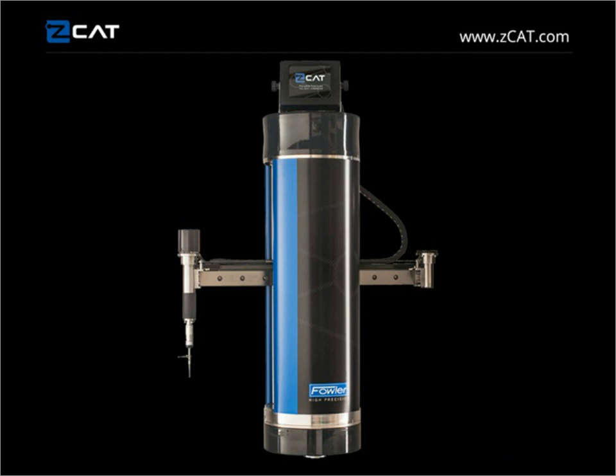So here gives you a little bit of a picture of the zCAT with the probe. We also have a cabling system that drives the zCAT. So the motors actually can drive the zCAT up and down the z-axis and obviously in the cross-axis to compensate for the x and the y-axis. We're using a very sophisticated cabling system on this. It's a high-strength stainless steel synchro mesh cable, and we're using it to drive three of the axes: the z-axis, the cross-axis, or the x and the y-axis.